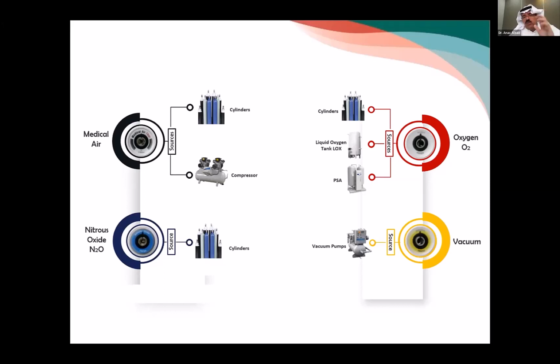The oxygen source comes from the cylinders. Some use liquid oxygen tanks, and some use PSA, which takes oxygen from the air, compresses it, and gets it. The medical air comes from the cylinders or the compressor, and you need to make sure you have the dryers and filters for it. The vacuum always comes from the vacuum pumps, and the nitrous oxide comes only from cylinders. So this is the general picture. We come and check it. If you have piped medical gas, you have to comply.